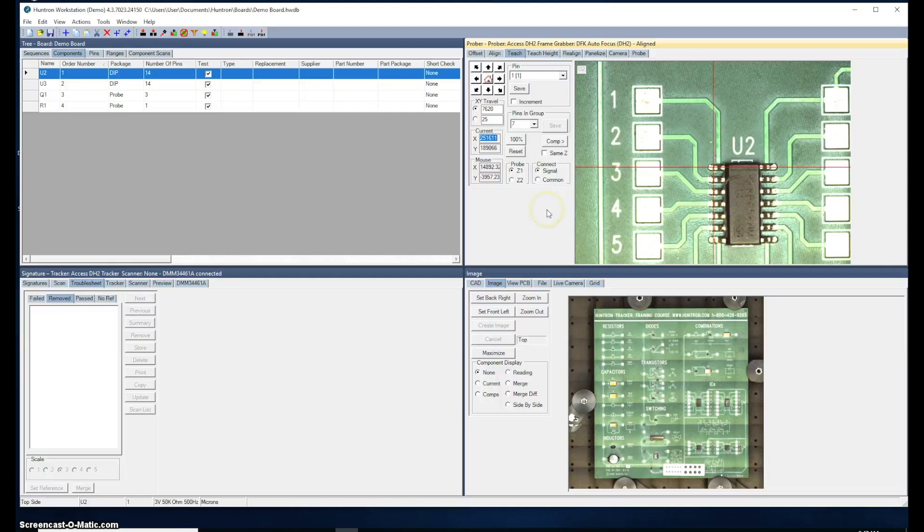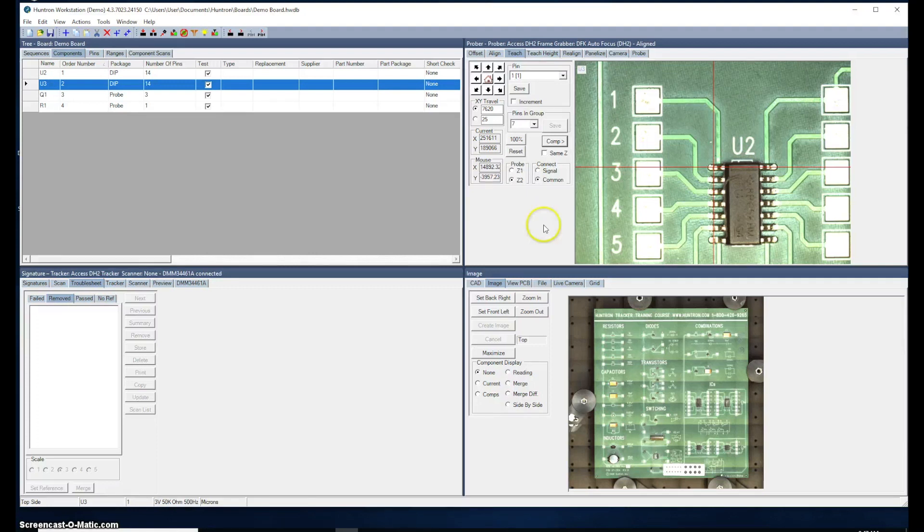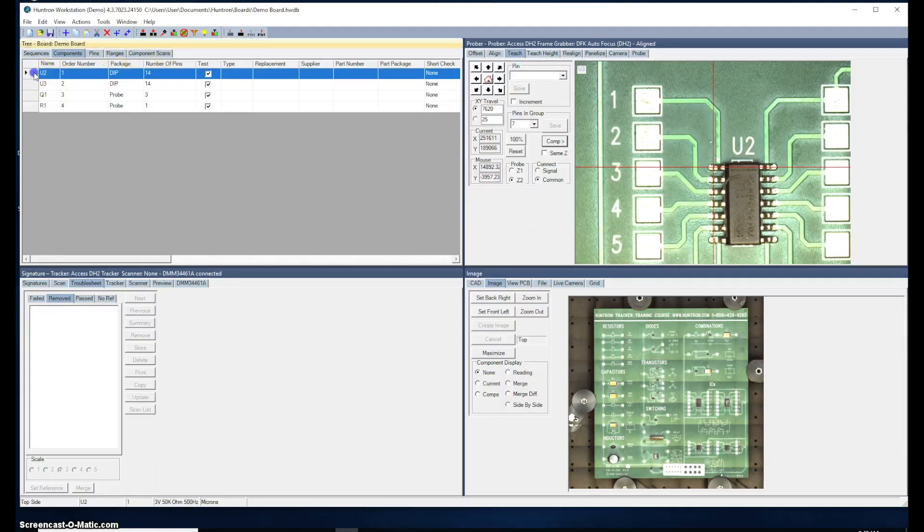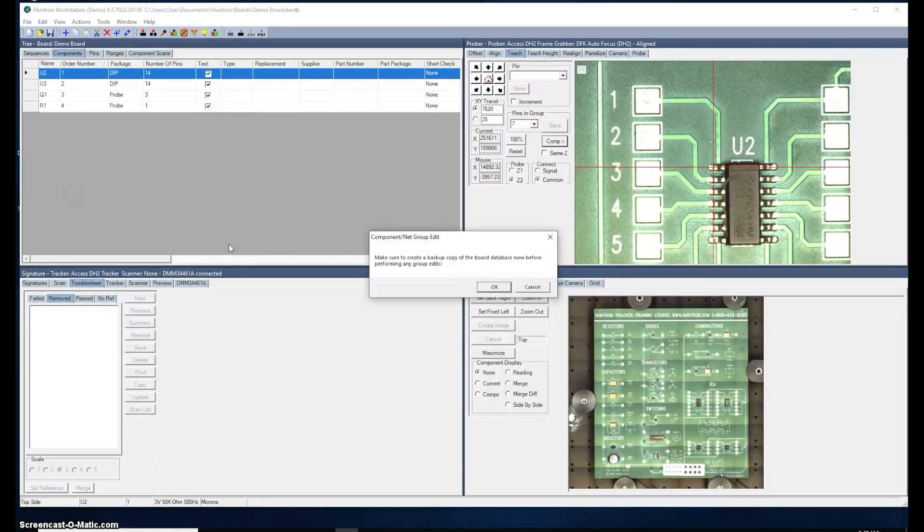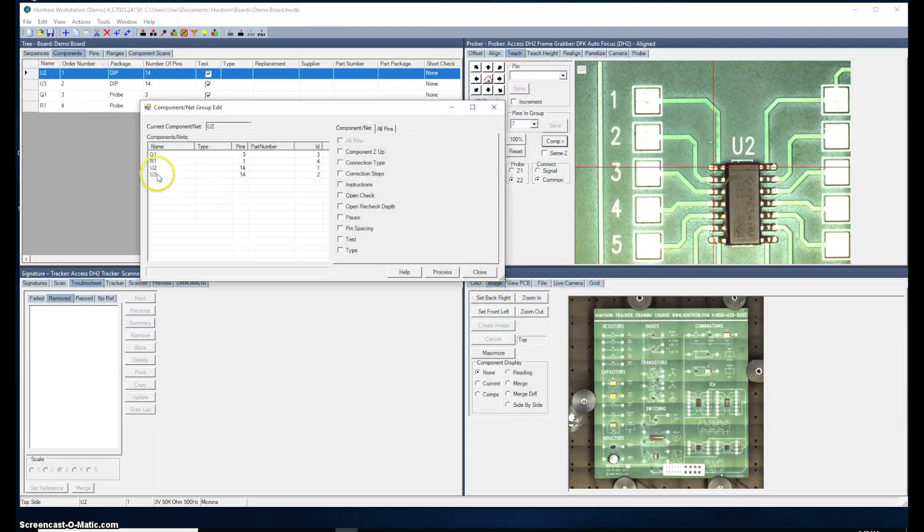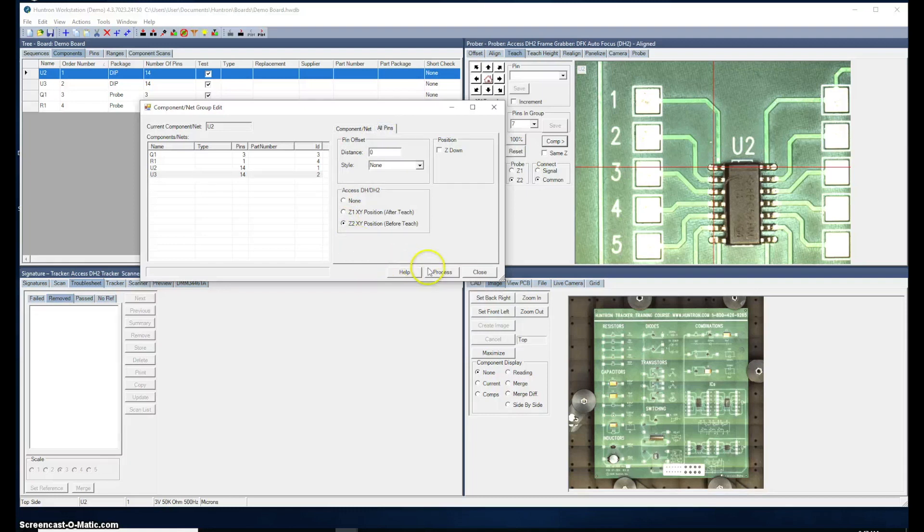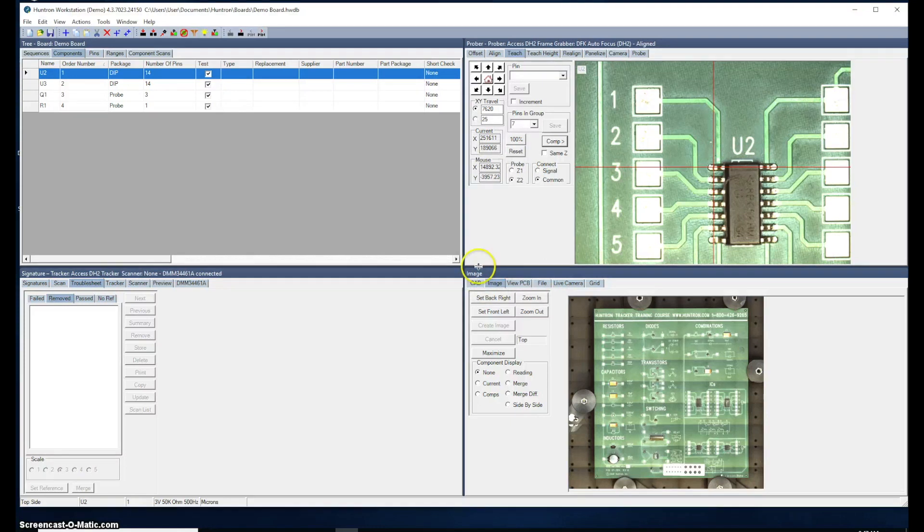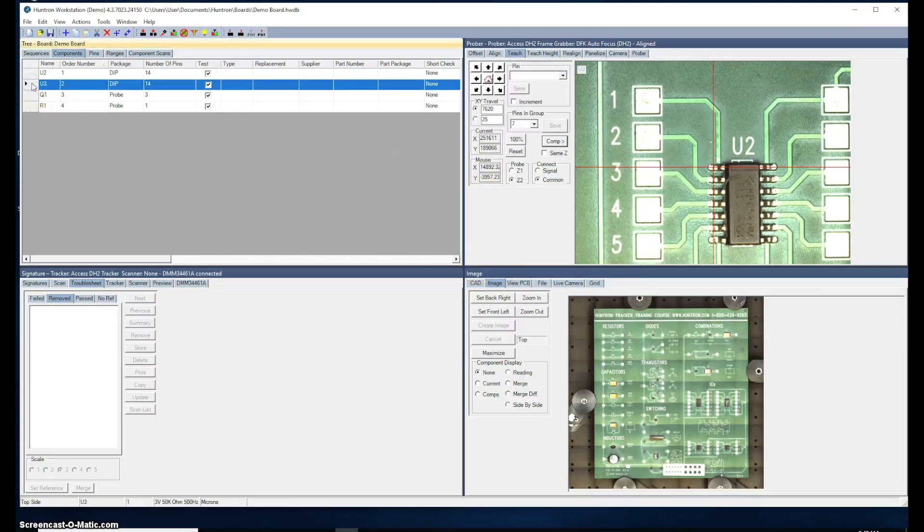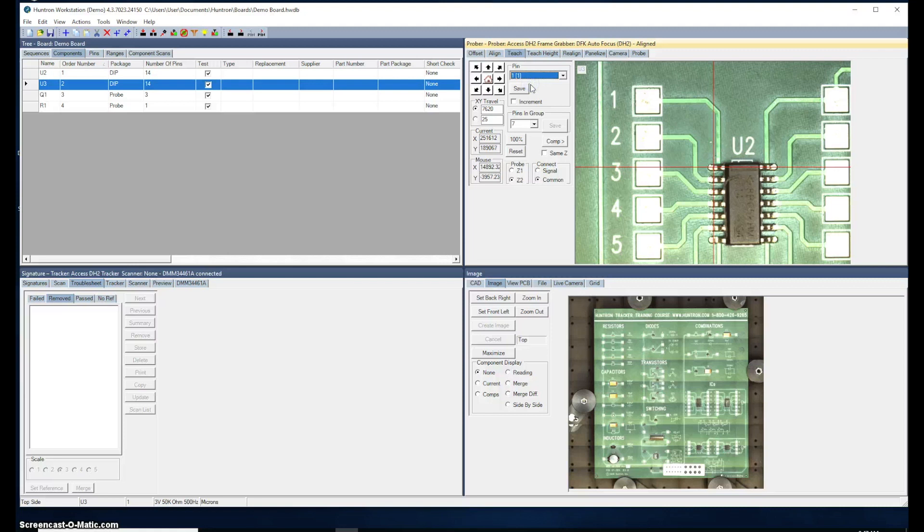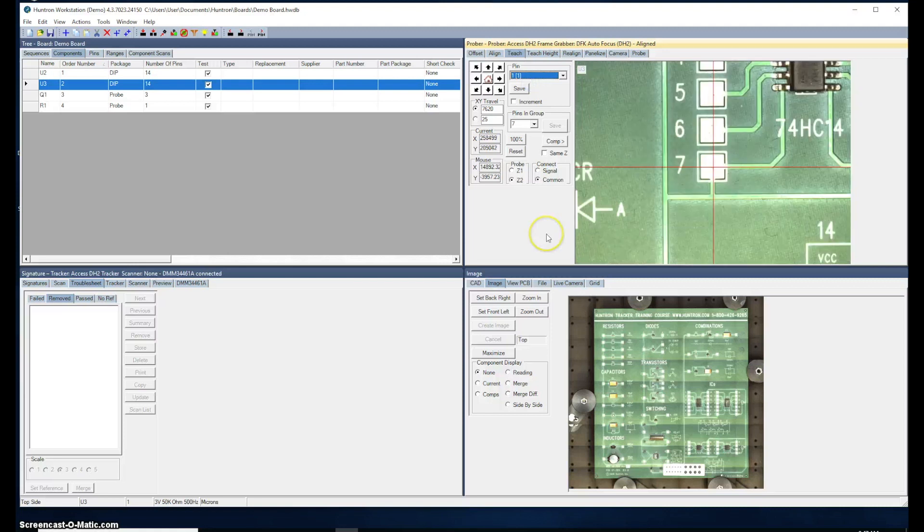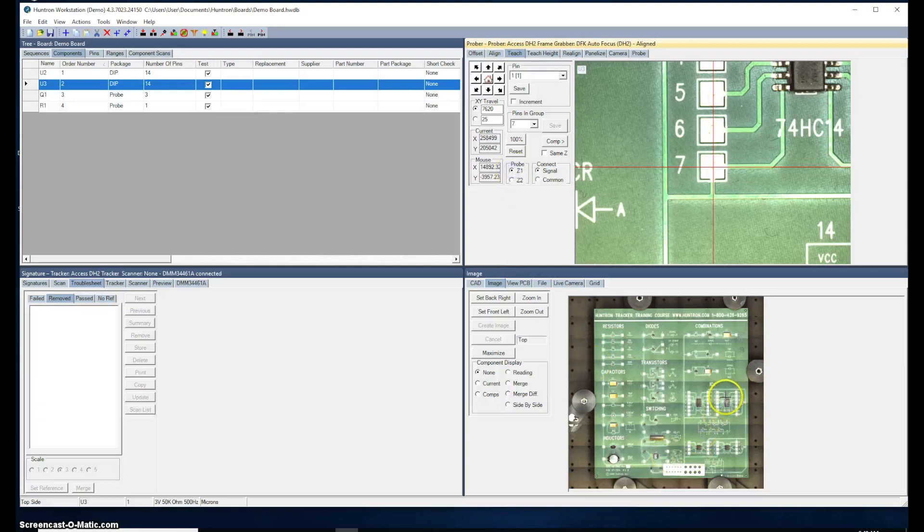Now we can move to U3. I want to copy the ground position or the Z2 position from U2 to U3 because I can use that same ground point with U3 as well. We'll come back here to U2, right click and select group edit. Select U3 in the list. Go to all pins and select Z2 XY position and click process. It will copy the Z2 position for U2 to U3 and that's complete. So now when I come back here to U3 and click pin one, notice it moves over there to the ground position that we used with U2, but this is now for U3. So now I no longer have to teach the Z2 position for U3. We can go straight to doing the Z1 position. That saves us a lot of time.